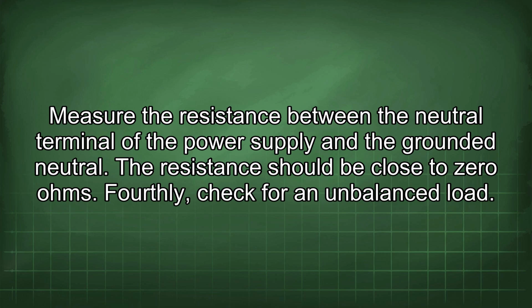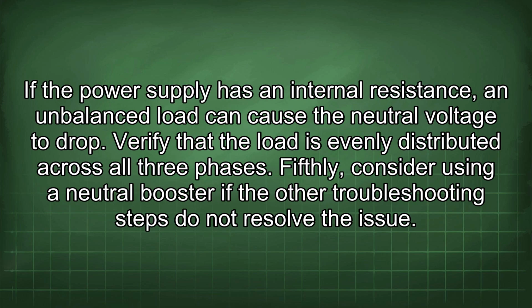Fourthly, check for an unbalanced load. If the power supply has an internal resistance, an unbalanced load can cause the neutral voltage to drop. Verify that the load is evenly distributed across all 3 phases.